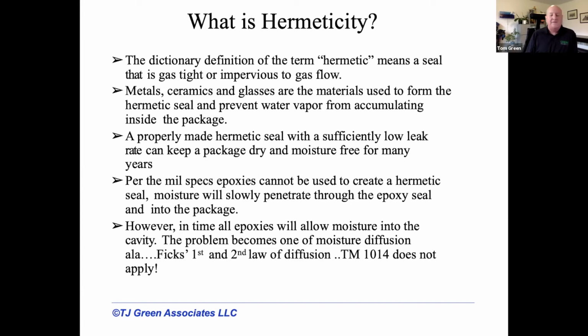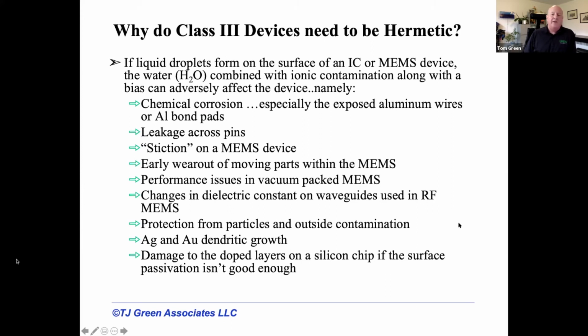But if you have epoxies in the leak path, then 883 test methods are not the right test to employ. That's a whole other problem. That's about moisture diffusing through a polymer, and that's a different approach altogether. That's what we call non-hermetic parts. But in a medical device, you've got a little bit of both once it's implanted in the body. You have a seal that you hope is hermetic, and then you do some subsequent processing and you hope that subsequent molding of the header doesn't compromise the seal. And then you put it in the body.